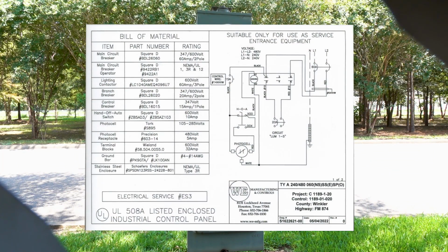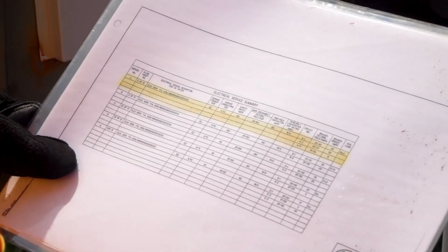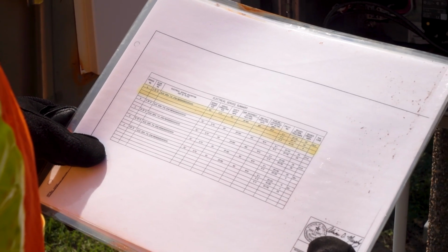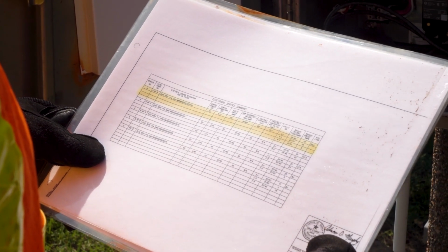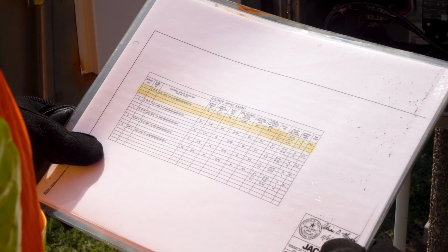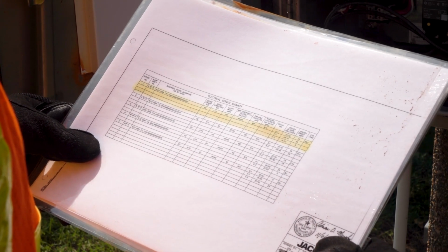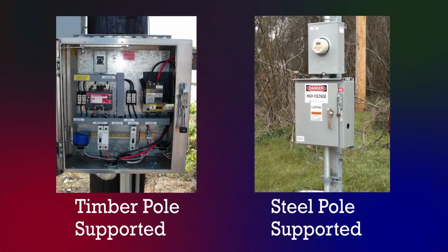The inspector will need to look at the unique line drawing provided by the UL 508 shop in the service's door pocket. Comparing the line drawing to the data chart in the plan set for that location, the inspector can verify that what was ordered and installed matches what is called for in the project's plans. The next item of inspection will be the mounting of the enclosure to the service support structure.